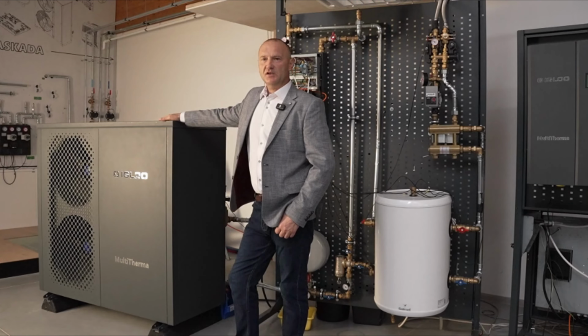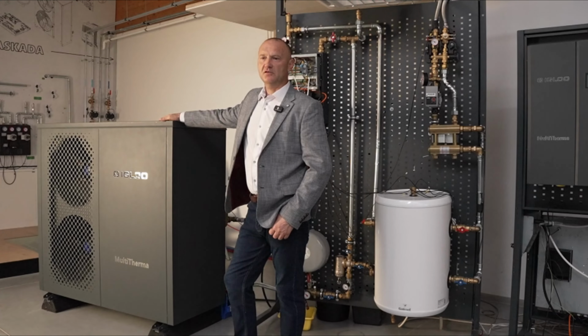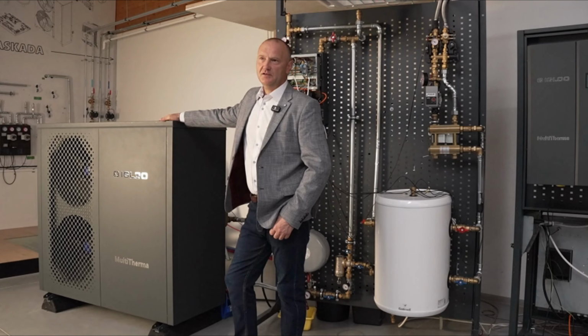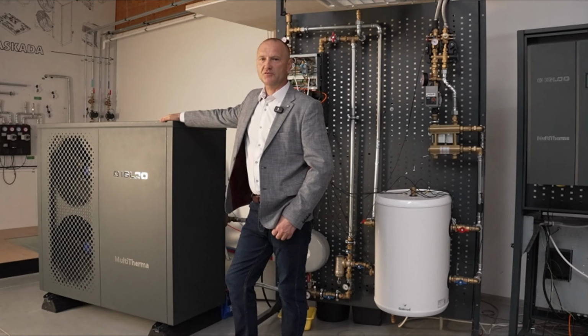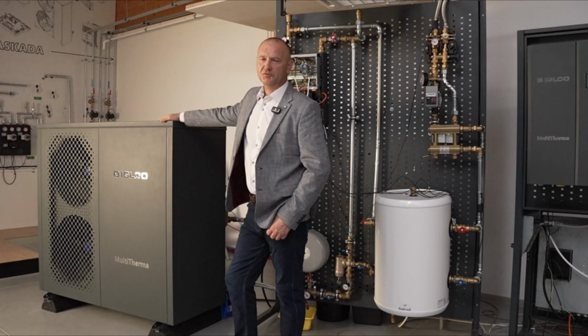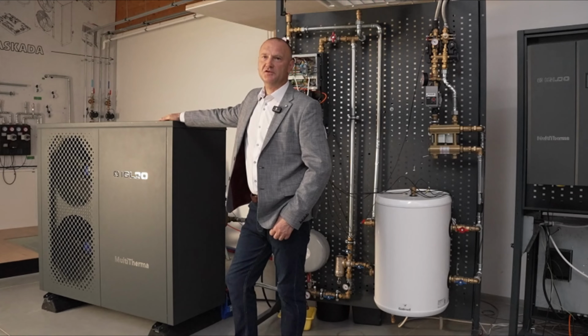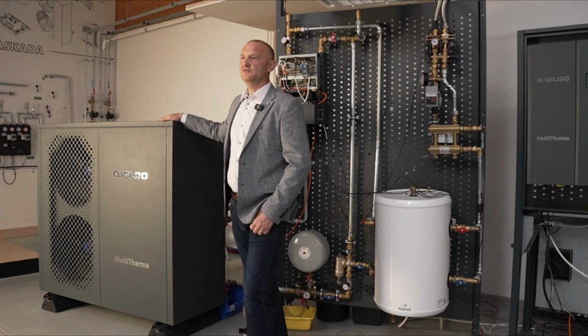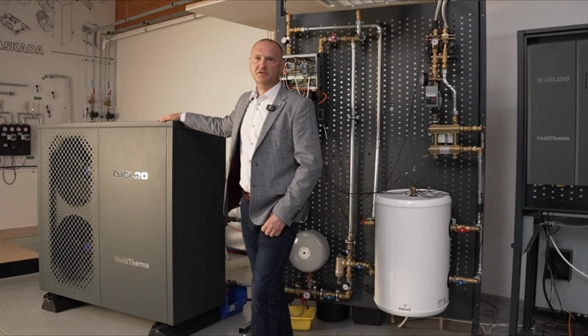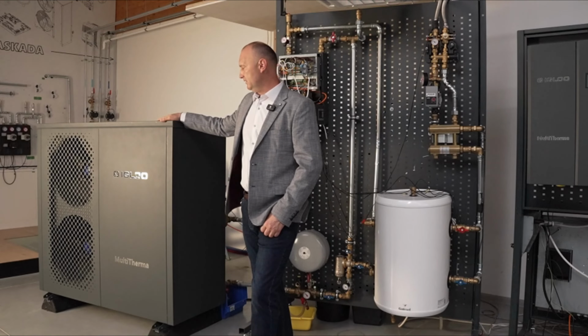Therefore, a unit like a 12 kilowatt model can also be appropriately selected for a building whose actual demand isn't necessarily 12 kilowatts, but perhaps 6 or 8 kilowatts. This poses absolutely no obstacle. Such a device can effortlessly operate year-round at a power of even 4 kilowatts or even below 4 kilowatts. So it is a very flexible device that can be adapted to a range of applications, and for all newly built homes whose energy demands are at a low level. It absolutely proves its worth and can be used even though it is nominally a 12 kilowatt device.